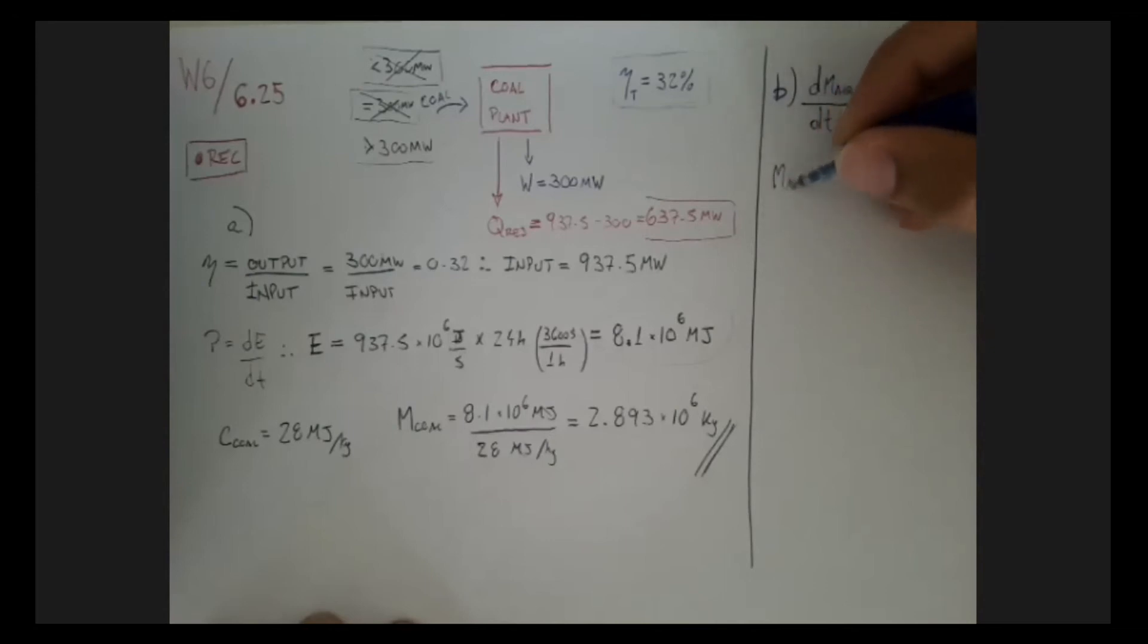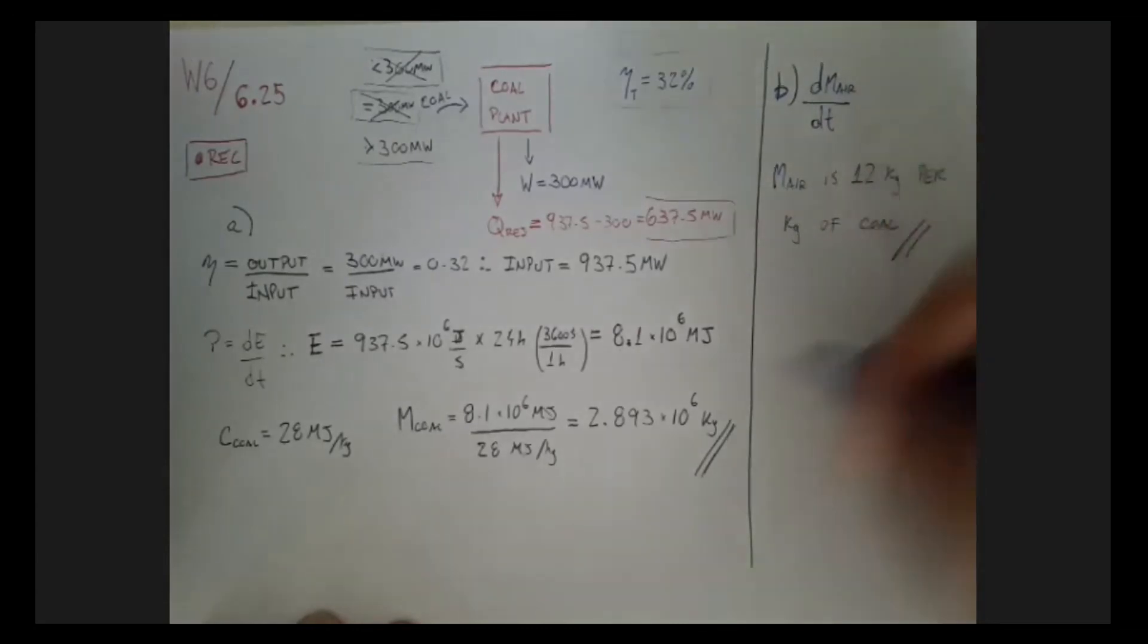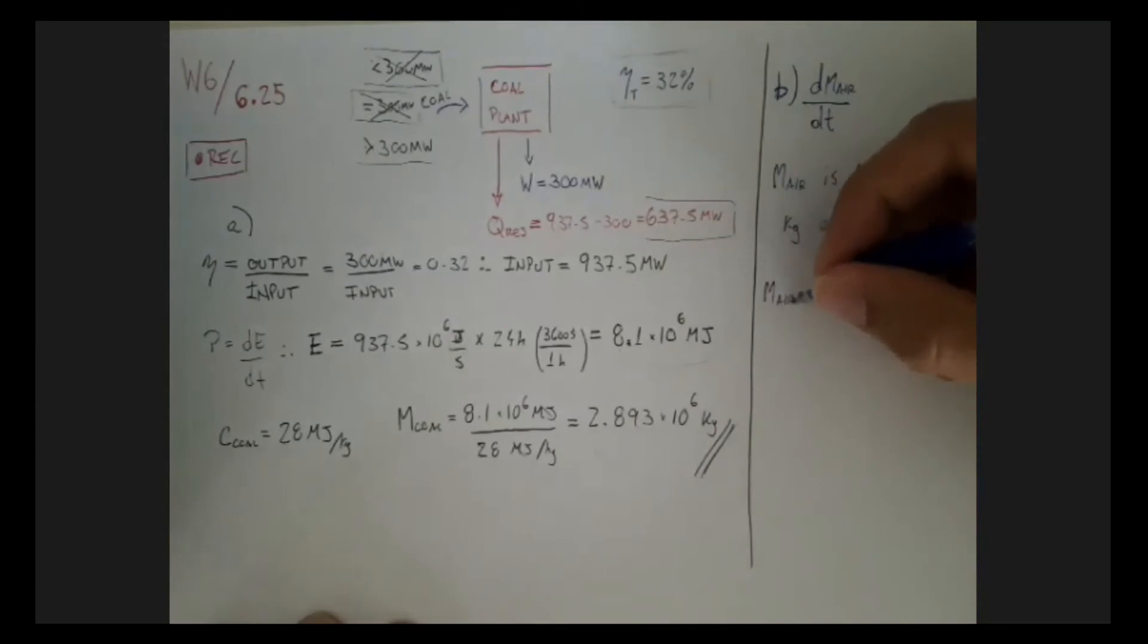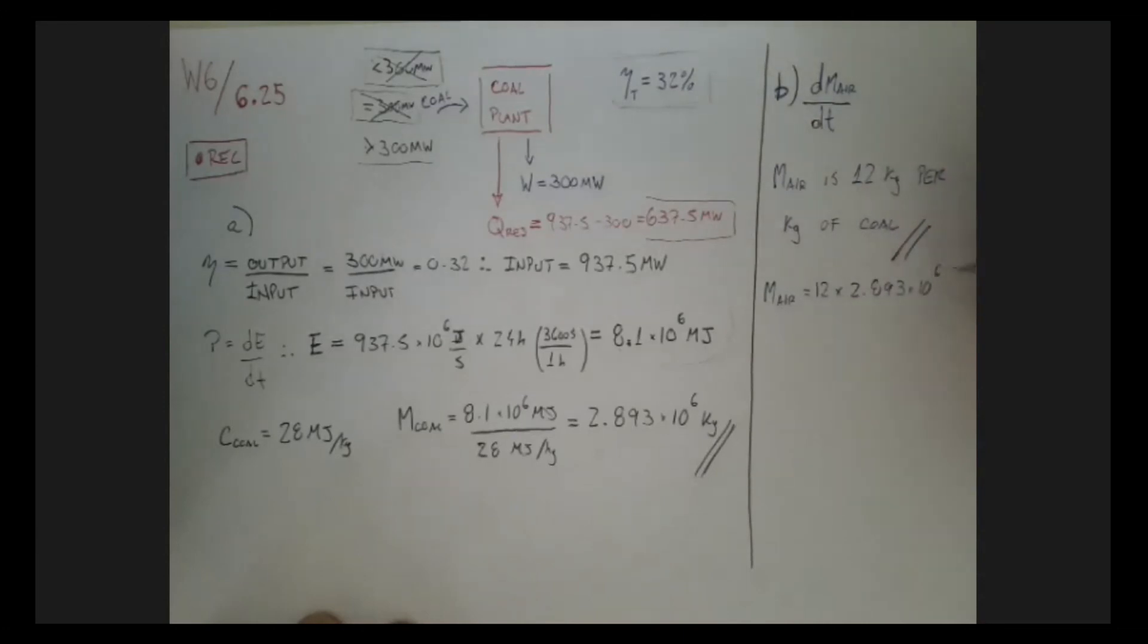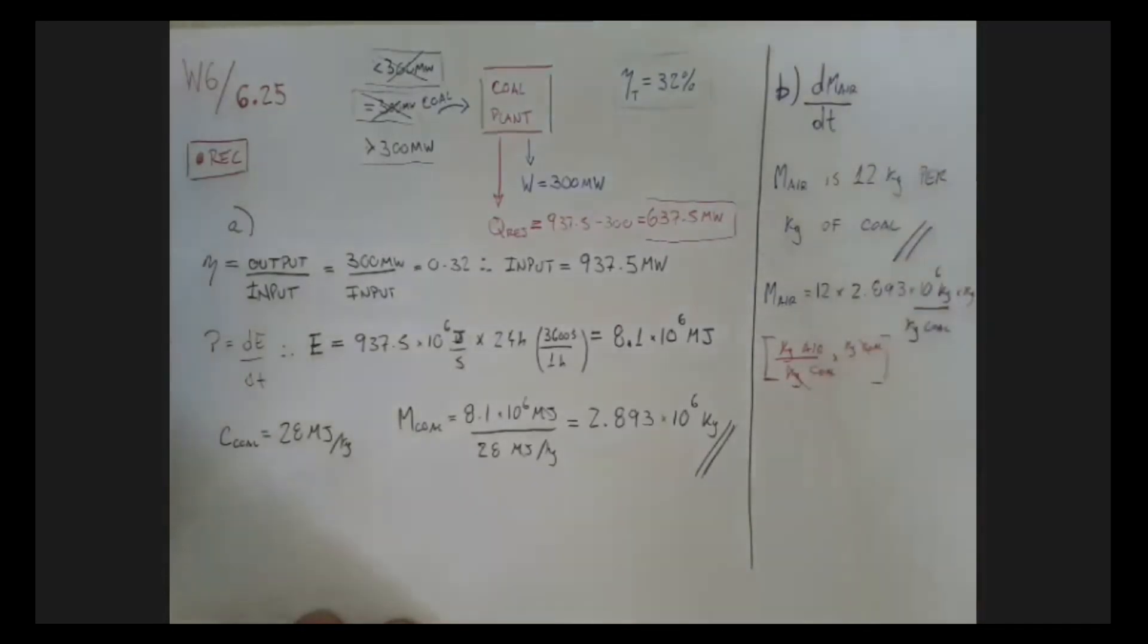We know that the mass of air required is 12 kilograms per kilogram of coal. So if we have this amount of kilograms of coal, just multiply one by the other. The mass of air will be 12 times the 2.893 times 10 to the 6. And note the units here. This is kilograms of air per kilograms of coal times kilograms of coal. So we're doing kilogram of air per kilogram of coal multiplied by kilogram of coal, so we've got kilograms of air.